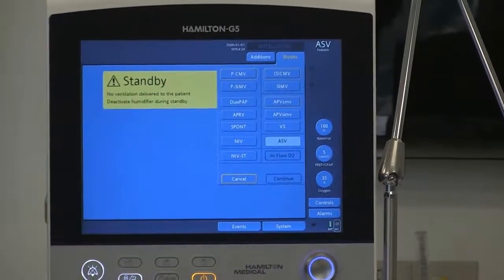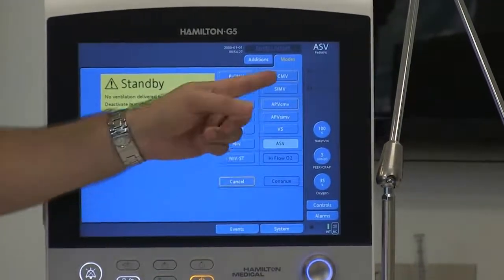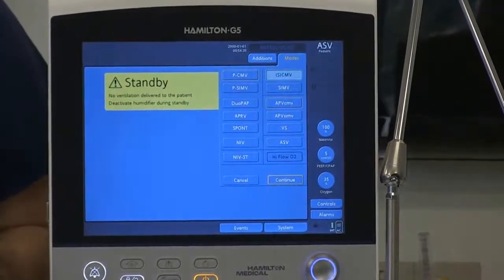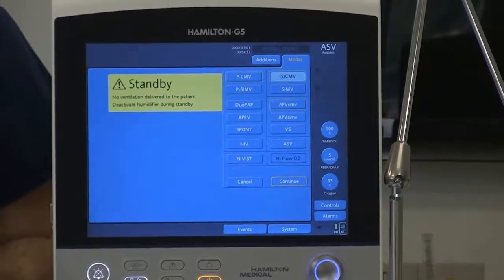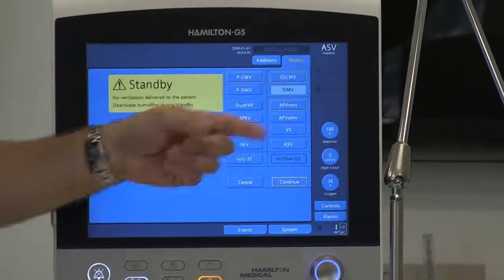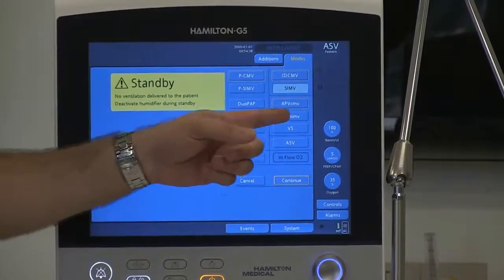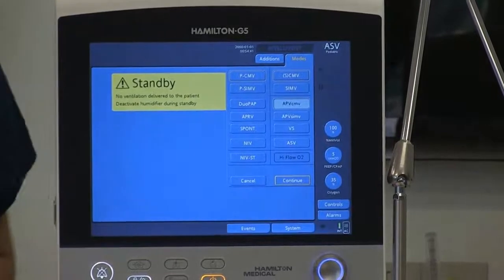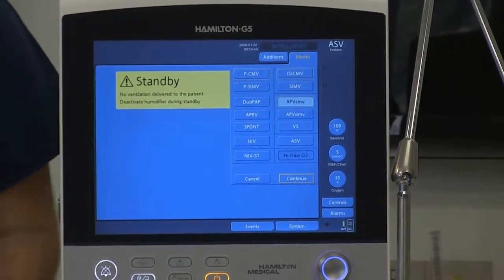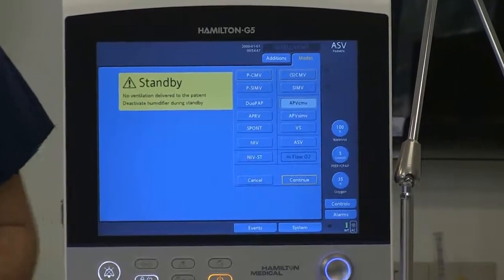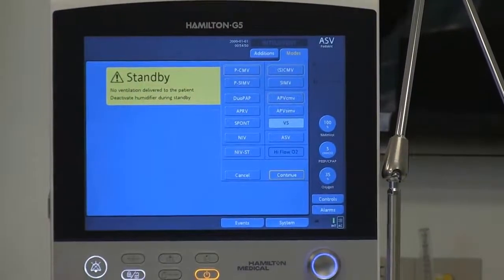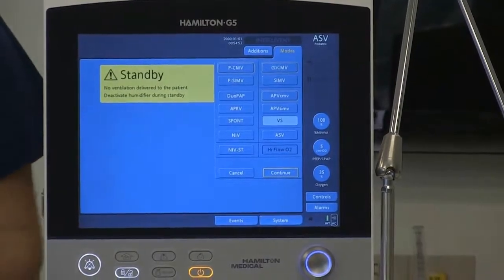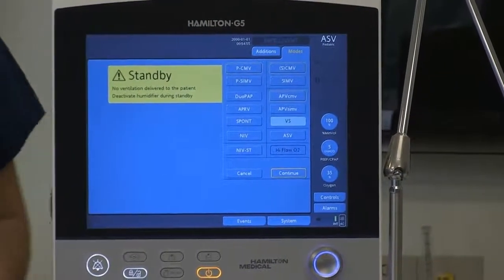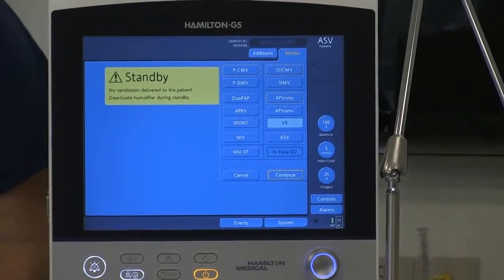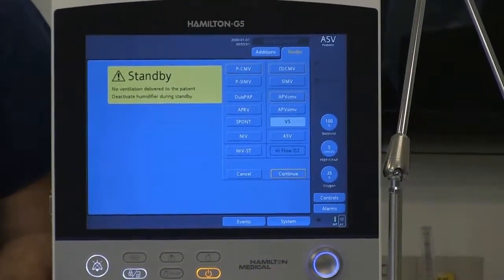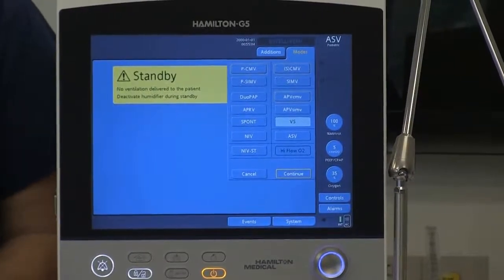Over here on the volume section, we have SCMV, which is your typical volume control mandatory ventilation mode. SIMV, which is volume SIMV. APV and APV-SIMV are variable flow volume targeted modes. VS, volume support, is another spontaneous mode. Instead of spontaneous, where spontaneous is targeted to a pressure, volume support targets a tidal volume, and your level of pressure support is variable depending on patient effort.